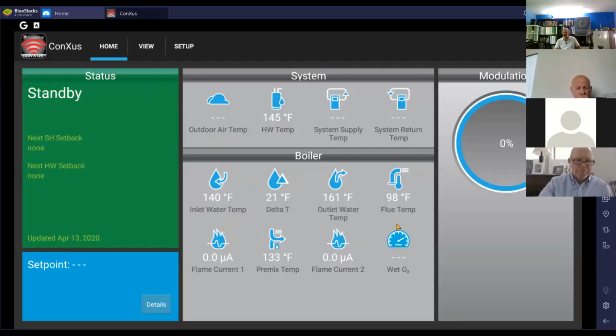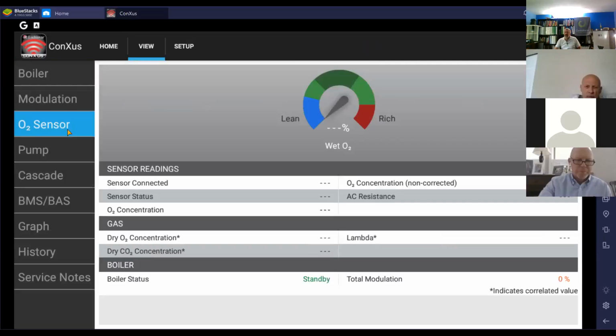So that's something new that's been added into the Crest as an option. You can actually get an idea of combustion remotely. That's an O2 sensor that's in there, and it's basically looking at it and it's going to let you know where that boiler is, as far as lean or rich. So you could see it remotely and also be like, hey, my boiler's operating out here where it shouldn't be.